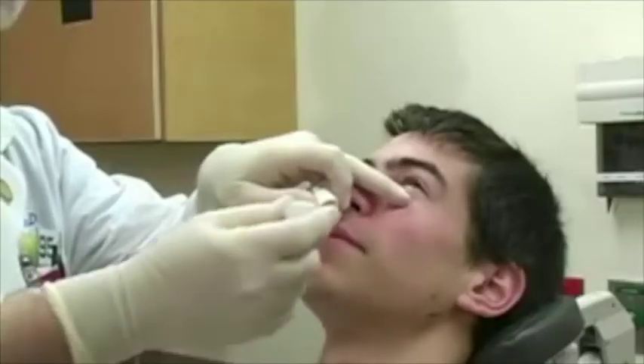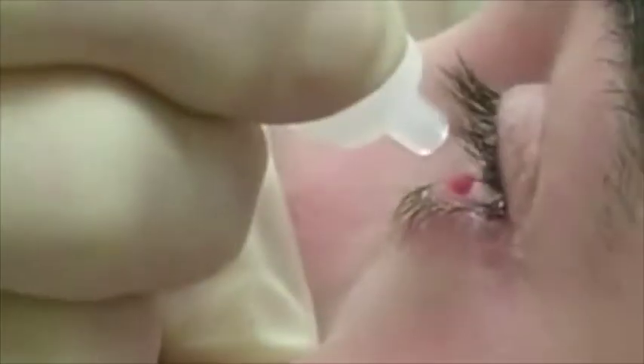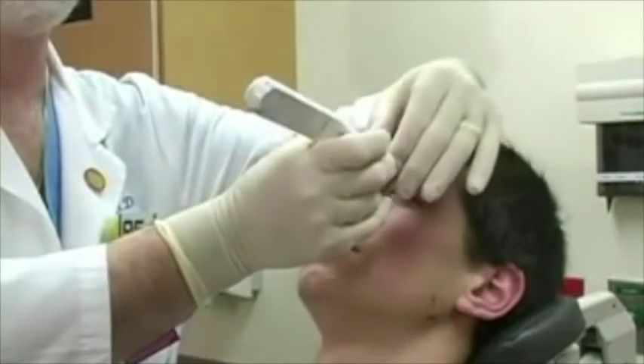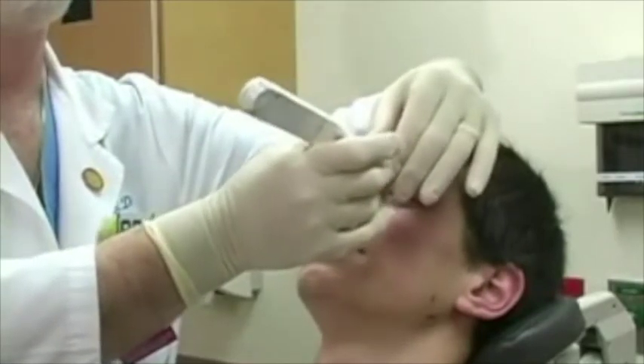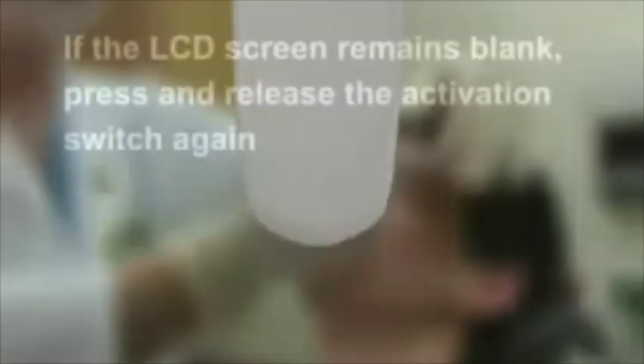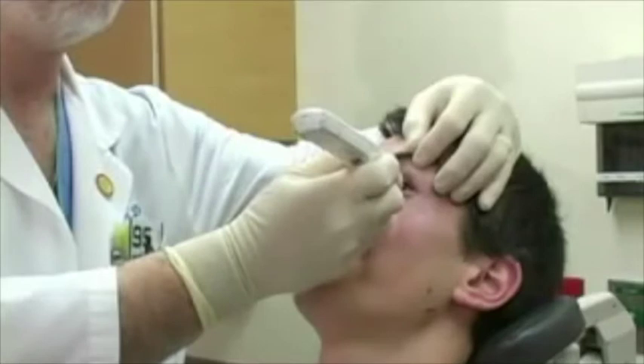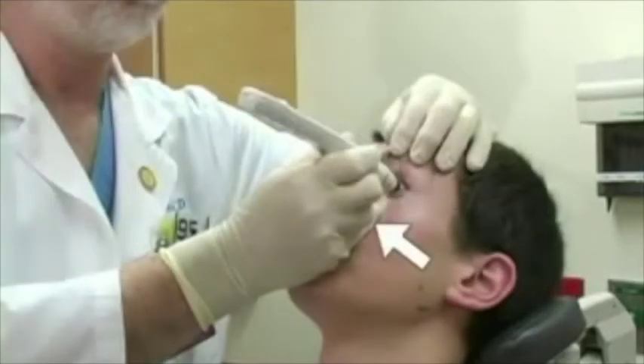Instruct the patient to look upward and place 2 drops of ophthalmic anesthetic into the lower ocular sulcus. Ask the patient to close his eye to prevent the anesthetic from leaking out of the orbit. Press and release the activation switch once to turn the Tonopen on. A beep will sound and 2 rows of bars will appear on the LCD. If the LCD screen remains blank, press and release the activation switch again. Hold the Tonopen like a pencil, perpendicular to the cornea. Rest the heel of the hand against the patient's cheek to provide stability.